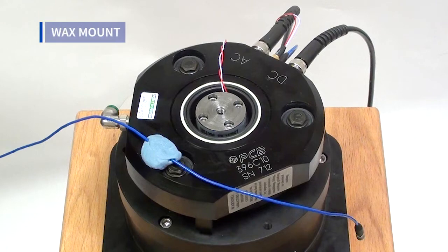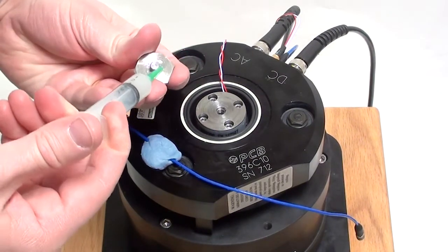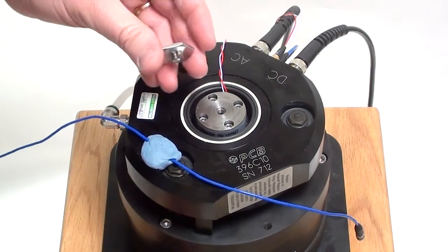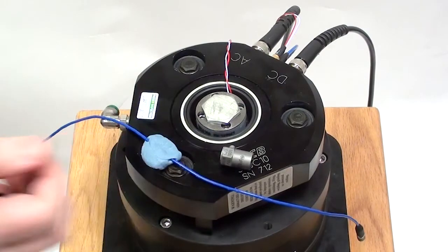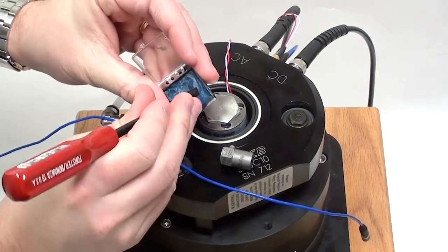For the wax mounting, an adhesive mounting base is stud mounted to the shaker with the techniques noted previously. A layer of petrowax is applied to the base of the accelerometer and it is pressed onto the mounting base.